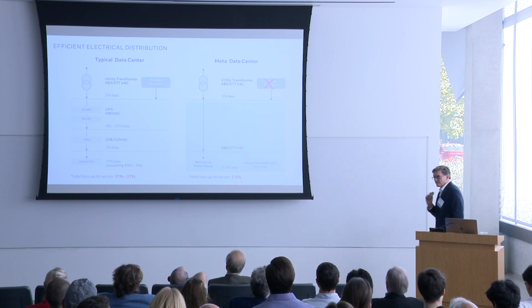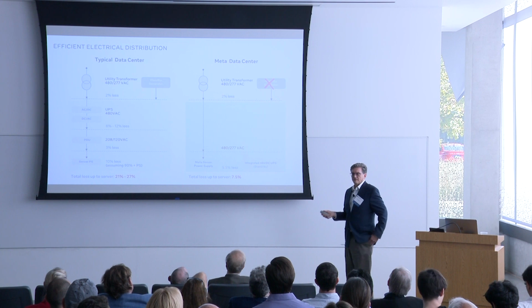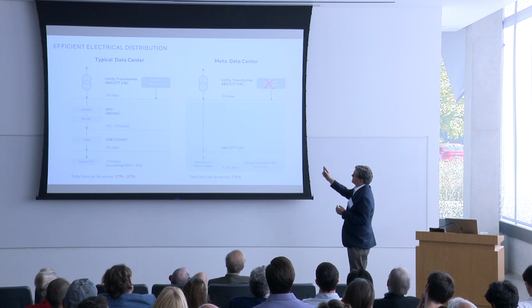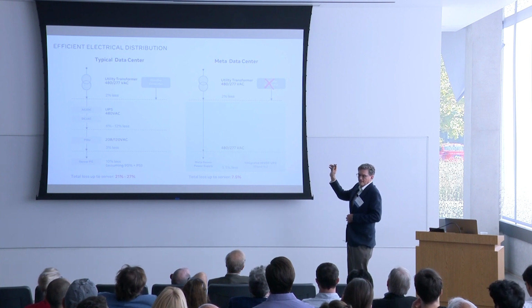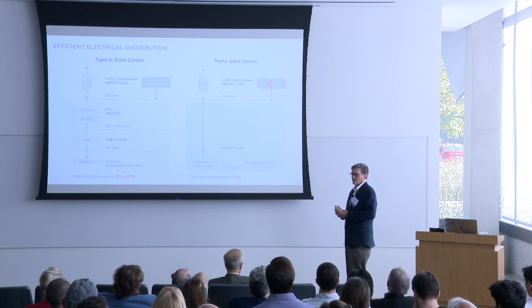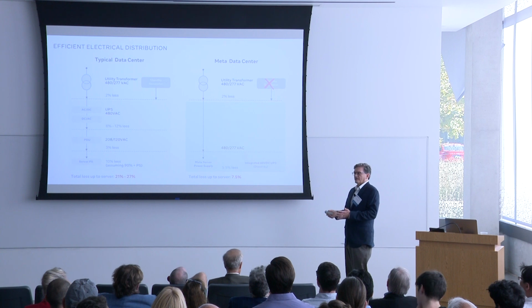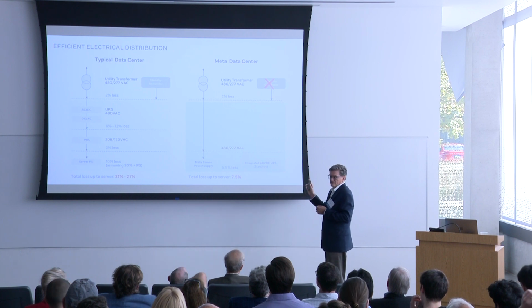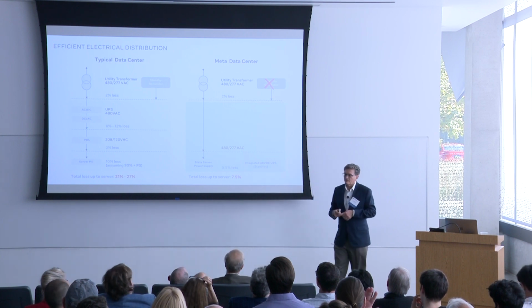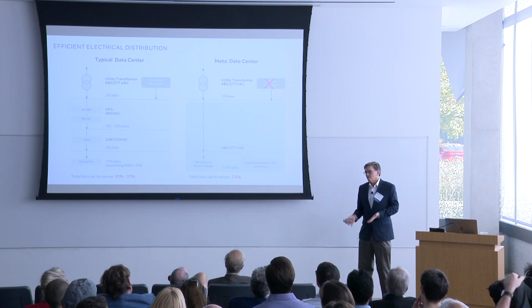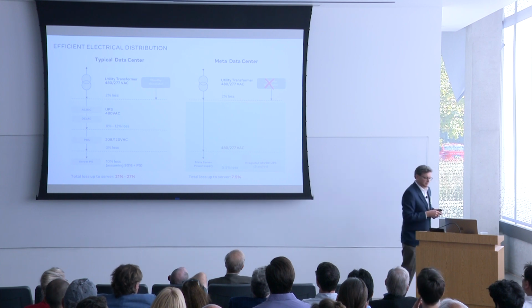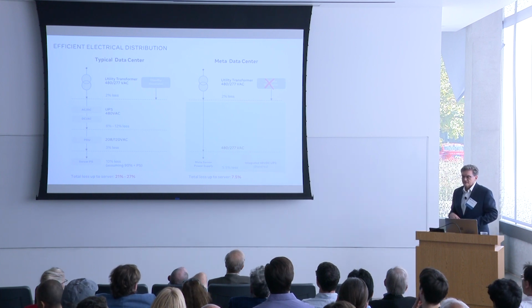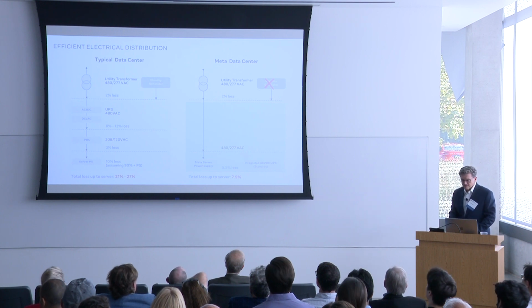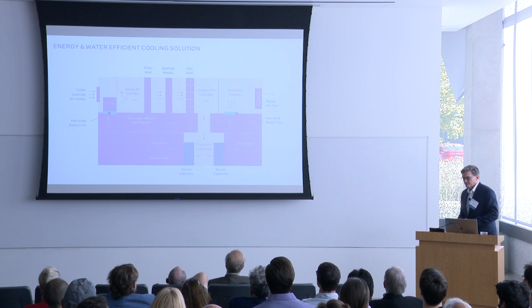One other brief point, one of the luxuries of owning the whole infrastructure stack is we can make intelligent decisions about things like backup. Every data center in the world, mostly, has a diesel generator backing it up just in case. We design our infrastructure with transmission grid power that's highly available, with multiple feeds and so on. So we're able to make calculated decisions that we actually don't need these generators, because the probabilities of failure are acceptably low, and we'll fail over to another site if that actually happens. That helps us in terms of carbon, CapEx, and all kinds of beneficial things. This is really difficult to do if you don't own that infrastructure.